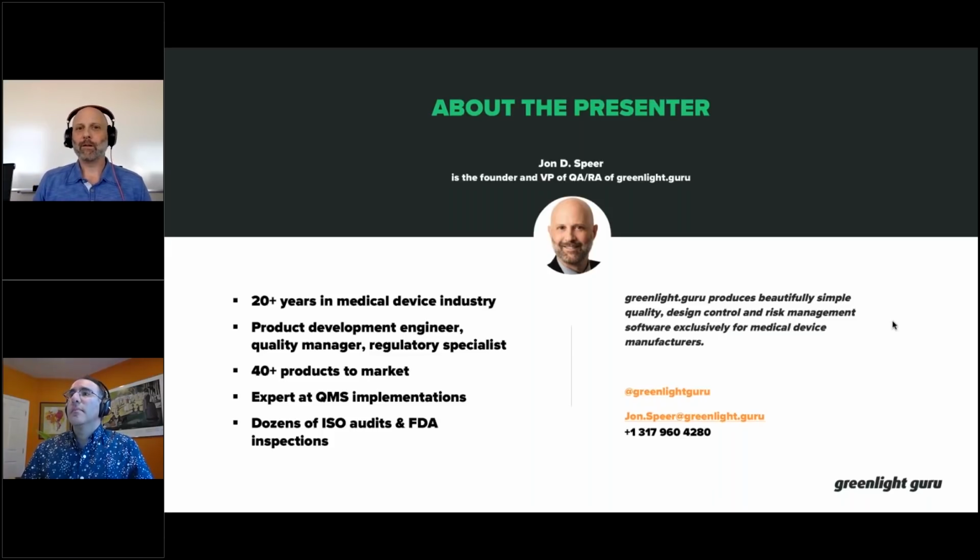Now, I believe that what you said, or your question about will FDA accept ISO 13485 certification as proof or evidence to comply with regulations, I believe we're on that path as an industry. In fact, I was at an event a few weeks ago where I actually heard FDA say, yes, that is where FDA wants to move towards, but we're a few years away from that being a reality.